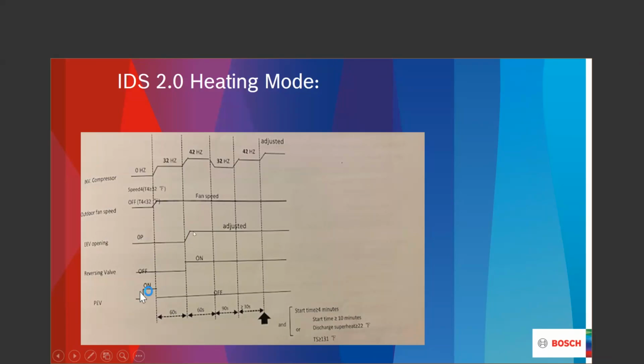Now we start our E valve being adjusted. Now we look at the fan speed. What are we doing? What's the temperature outside? What is T4 telling us? Is it below 32? Is it above 32? And so at that point in time, we start the capability of adjusting that outdoor fan motor. Take a look at my starting hertz, 32 for 1 minute. Then we went up to 42 for 1 minute. Then we dropped back down to 32 for 1.5 minutes.